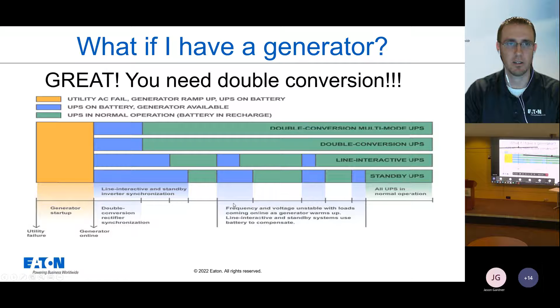So if you have a generator on a building, make sure you're putting in a double conversion UPS. Something to think about: your MDF, you're probably going to know if you have a generator on that, but it's important to know that on those network closets, maybe you do have generator power going to those closets. You might think, hey, I've got this little network rack over in the corner, no big deal, I'll just put a line interactive UPS on it. That could be fine if all you have is a single piece of networking equipment on it. But to be safe, I'd stick that double conversion UPS on it. It's going to play much nicer with the generator than going with line interactive.